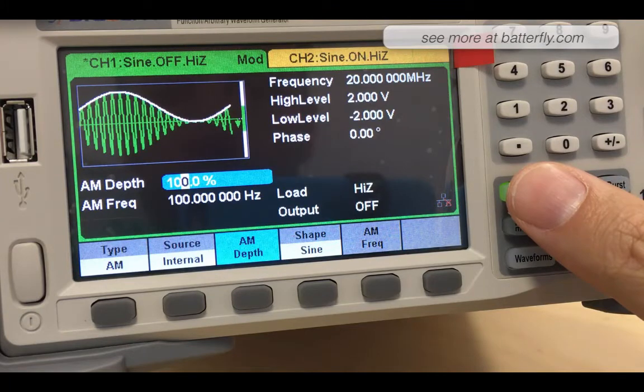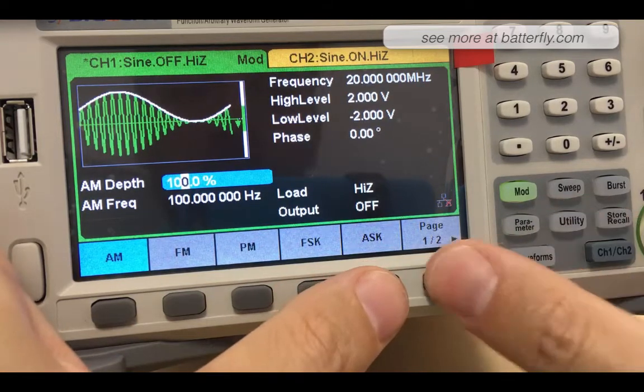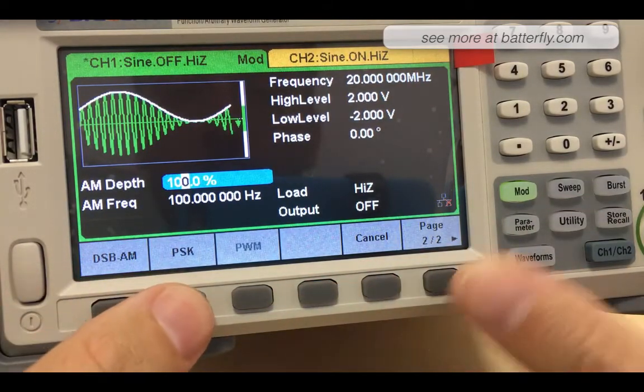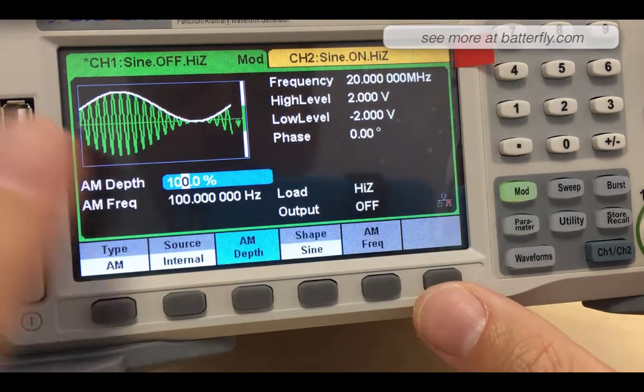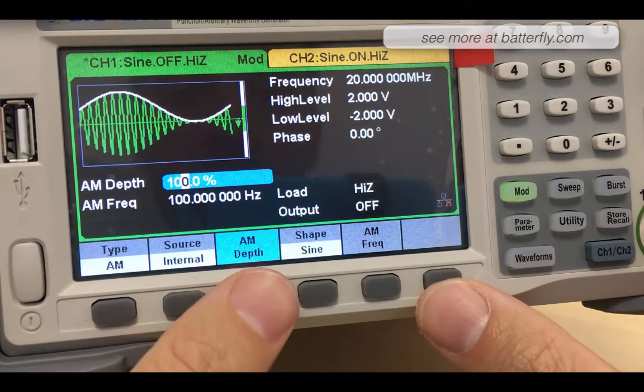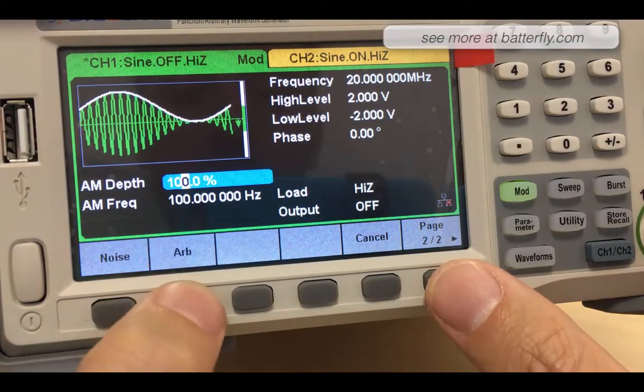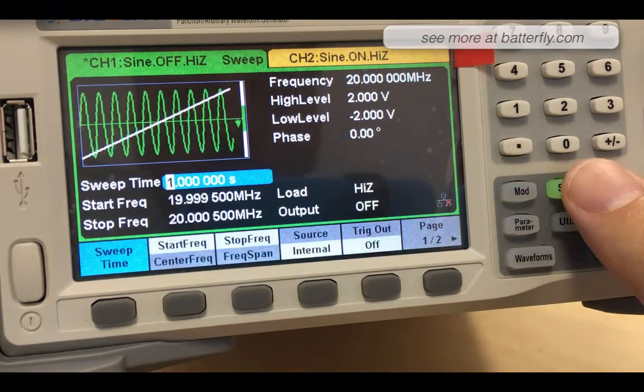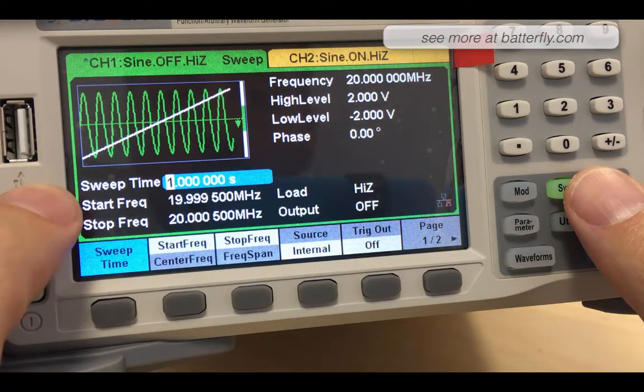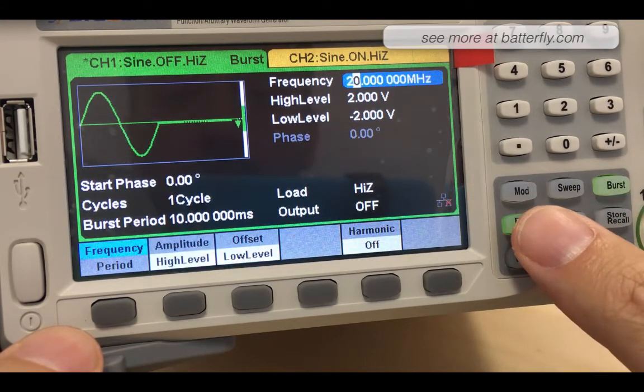We can change the modulation type: AM, FM, PM, FSK, ASK, DSB-AM, PSK. Source can be internal or external, with AM depth and shape options including sine, square, triangle, up ramp, down ramp, noise, and arbitrary. The unit is very easy to navigate. We have the sweep button where we can set sweep time, start frequency, and stop frequency.